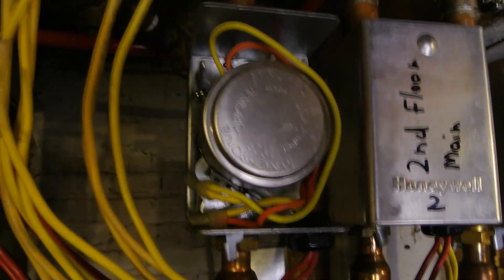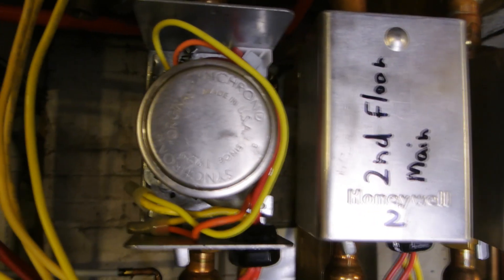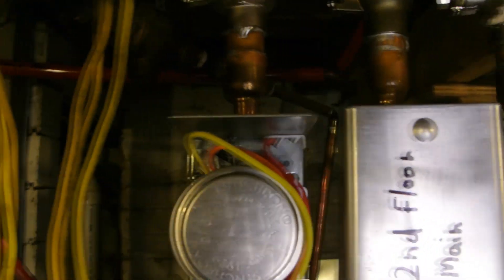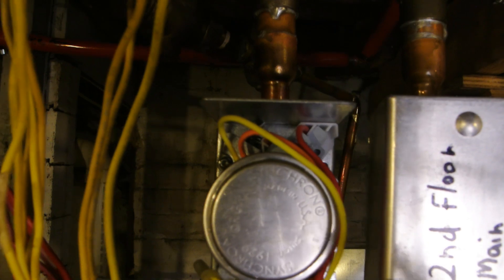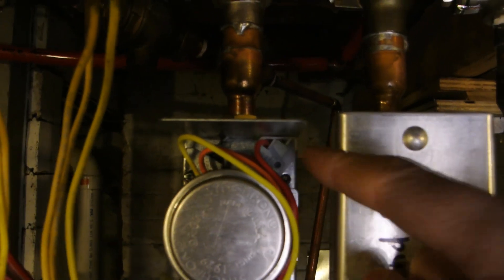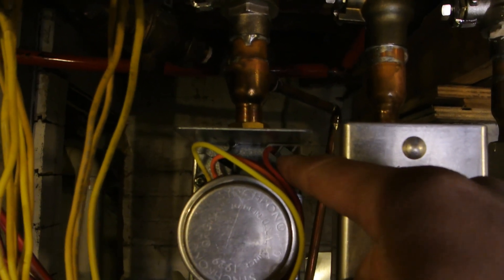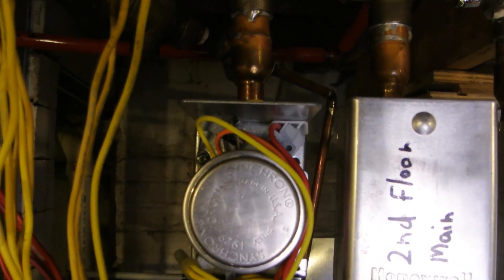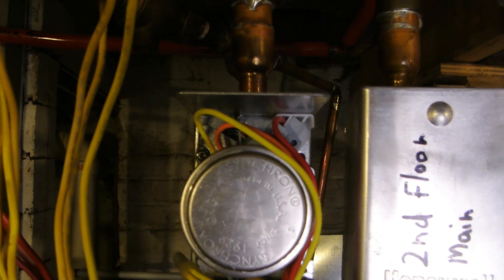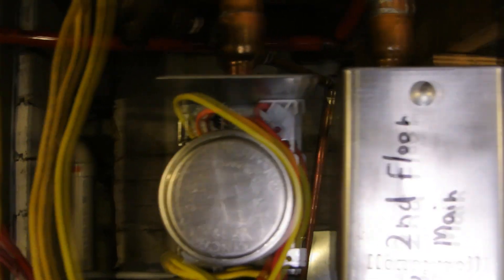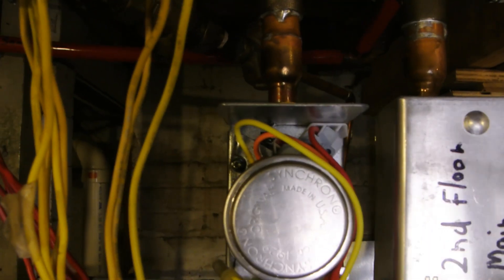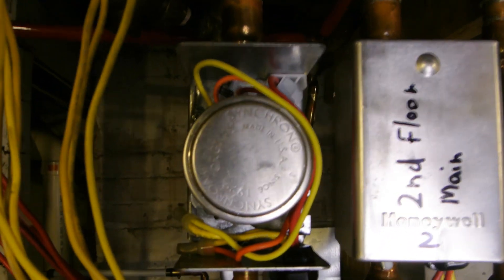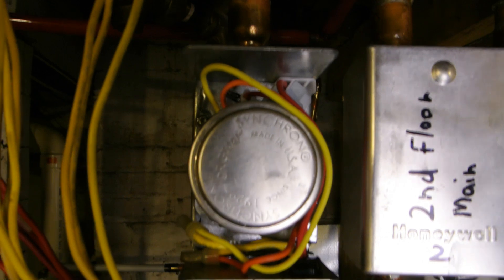It keeps the valve open and allows water to flow through. Another part of the valve, the third part, is this end switch. It's a micro switch, essentially like a light switch except it's spring-loaded. It clicks when it turns on. When it's turned on, it completes a circuit as well, which tells the boiler to turn on. They call that an end switch.